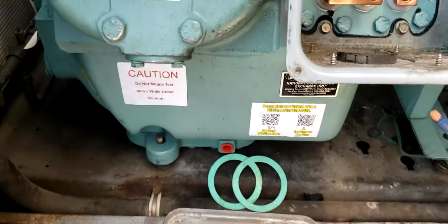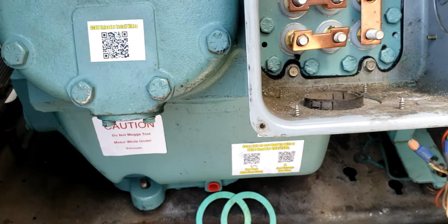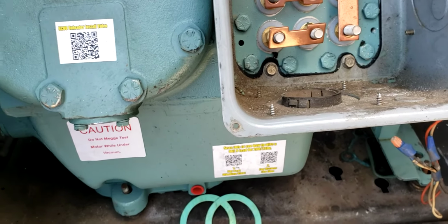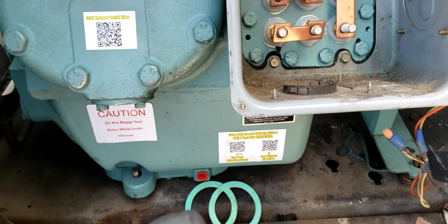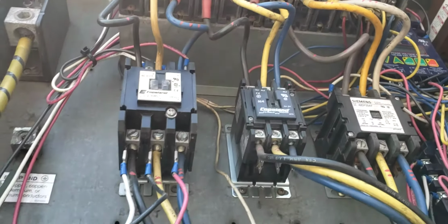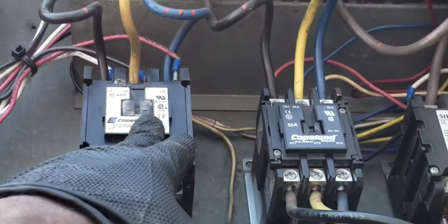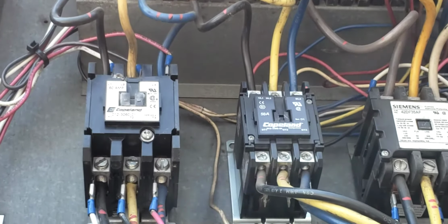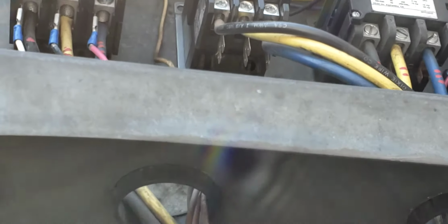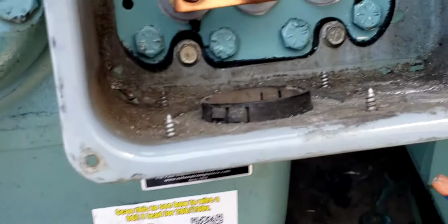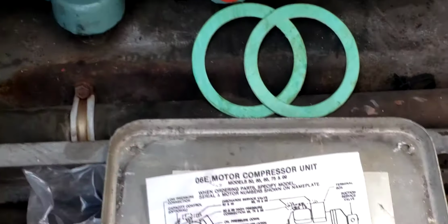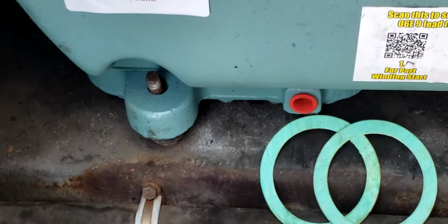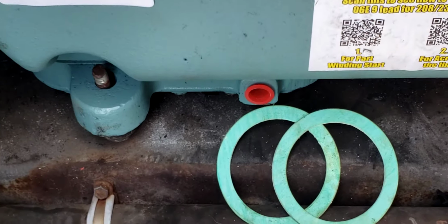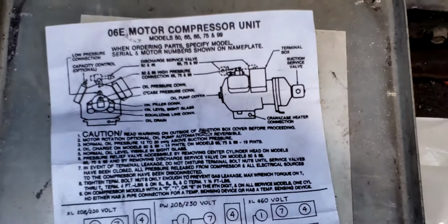They won't pull in simultaneously. Contactor 1 will pull in maybe a tenth of a millisecond before contactor 2, so you probably won't see it if you're watching. If you're looking with the naked eye, it'll appear they both pulled in simultaneously, but they didn't. Contactor 1 pulled in just a bit before number 2. That's the reason for part winding - you use less inrush or locked rotor current for initial startup.